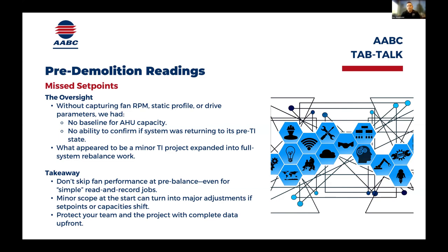So having that point of reference to say, no, look, I took this point of reference, it was 1.2 inches of static, and now it's 0.8 inches of static. Something changed. So I would say documenting outdoor conditions may come in handy also.